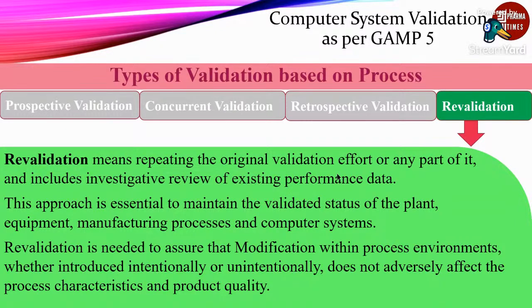Revalidation is needed to assure that modification or any changes are there during operation. So revalidation ensures whether any functionality is added or removed from the system, or it is not working properly. So during revalidation, we find out the gaps between the current scenario of the validation to fulfill our requirement and to comply with the regulatory agency. So revalidation generally happens based on criticality of the system and the functionality of the system.